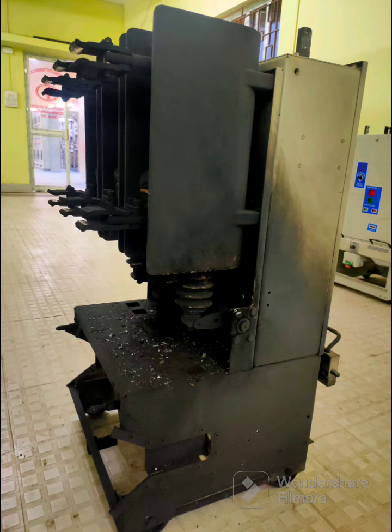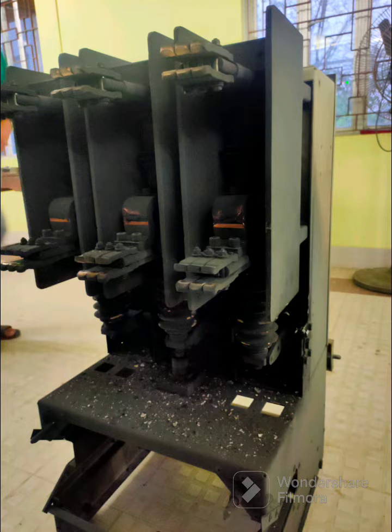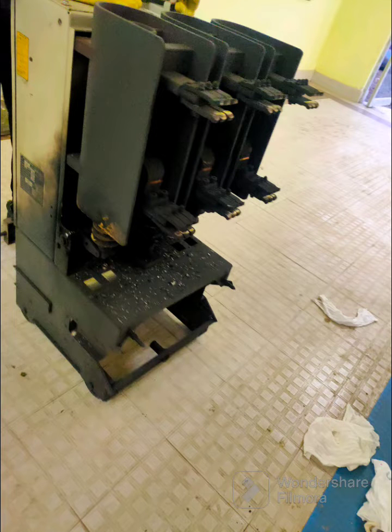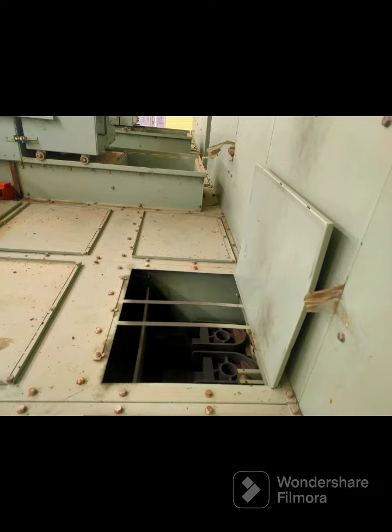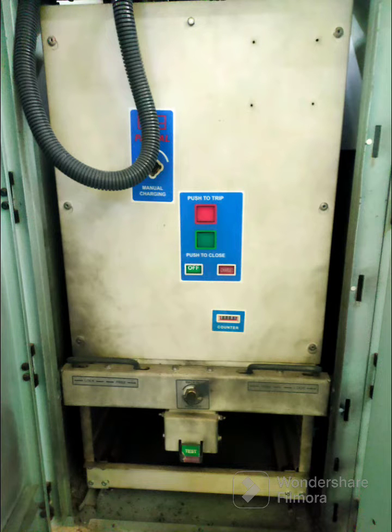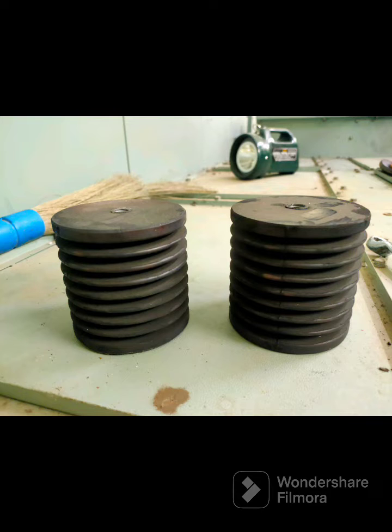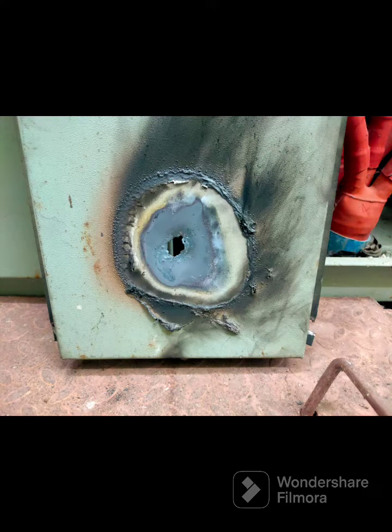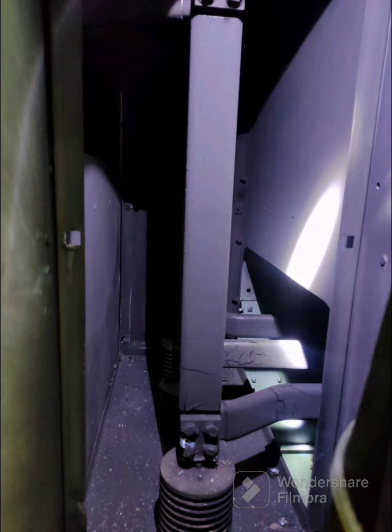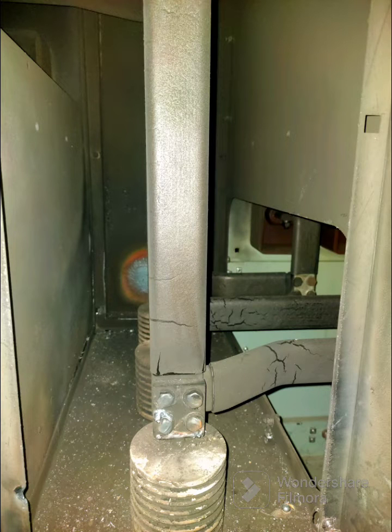The topic being discussed is an 11 kV breaker explosion. The pictures you are seeing show the exploded 11 kV breaker caused by the fault, with the explosion and bursting out of carbon and the affected panels. The pictures also show the affected bus bars, the carbon depositions, and so on, here and there. You can easily see that.